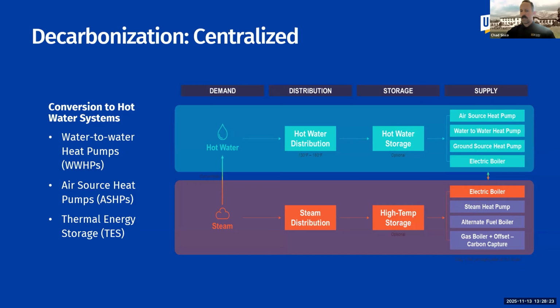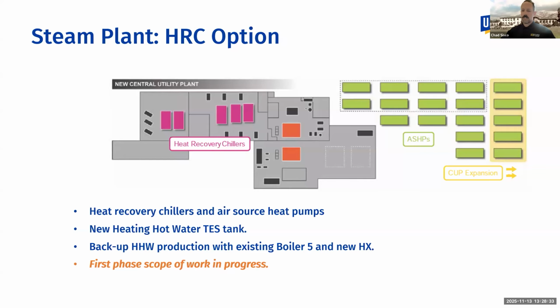But after consideration, our preferred option is scenario 1.2, heat pump technology with hot water thermal energy storage, if you guys reference our study. So I won't go into this study too much here. But evaluation criteria for the study included GHG emissions reduction, life cycle cost, annual peak resource use, resilience and reliability, ease of implementation, and a few others. In our preferred scenario, steam building systems would be replaced with low temp hot water, requiring heating coil, pipe, pumps, heat exchanger replacements in a phased approach.